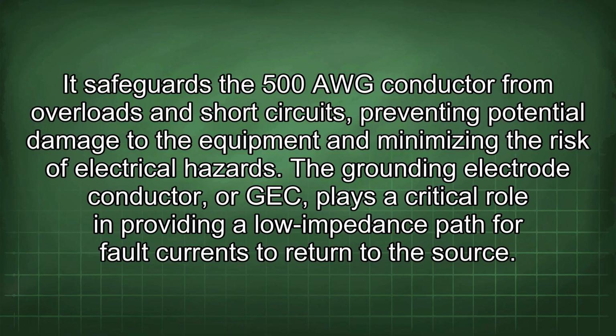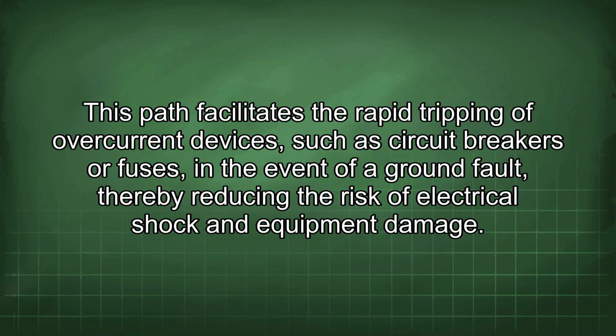The 400 amp service disconnect acts as the primary overcurrent protection device for the entire tap system. It safeguards the 500 AWG conductor from overloads and short circuits, preventing potential damage to the equipment and minimizing the risk of electrical hazards. The grounding electrode conductor, or GEC, plays a critical role in providing a low impedance path for fault currents to return to the source. This path facilitates the rapid tripping of overcurrent devices such as circuit breakers or fuses in the event of a ground fault, thereby reducing the risk of electrical shock and equipment damage.